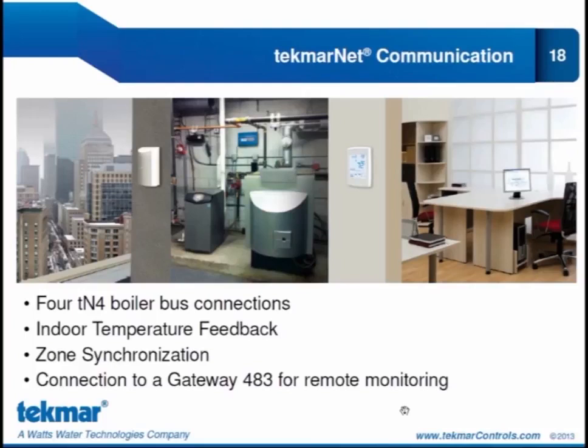So with all those tekmarNet devices connected to the boiler buses, we can have indoor temperature feedback to the system, and we can also have zone synchronization on our system. Of course, we can also connect to a gateway control, a 483 if we want to remotely monitor our system and adjust our thermostats, or a 482 if we're trying to configure our system to be compatible with the home automation system.